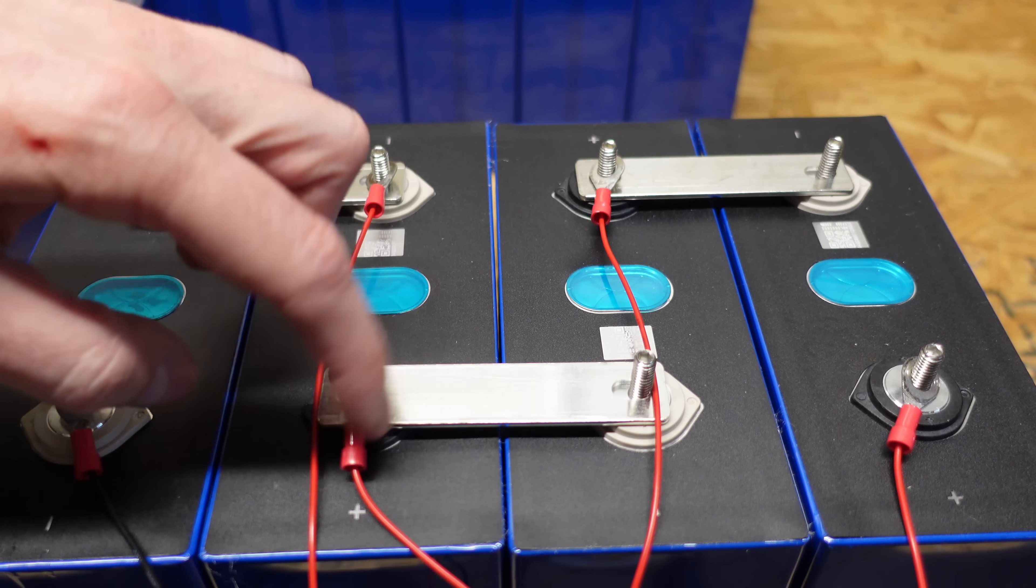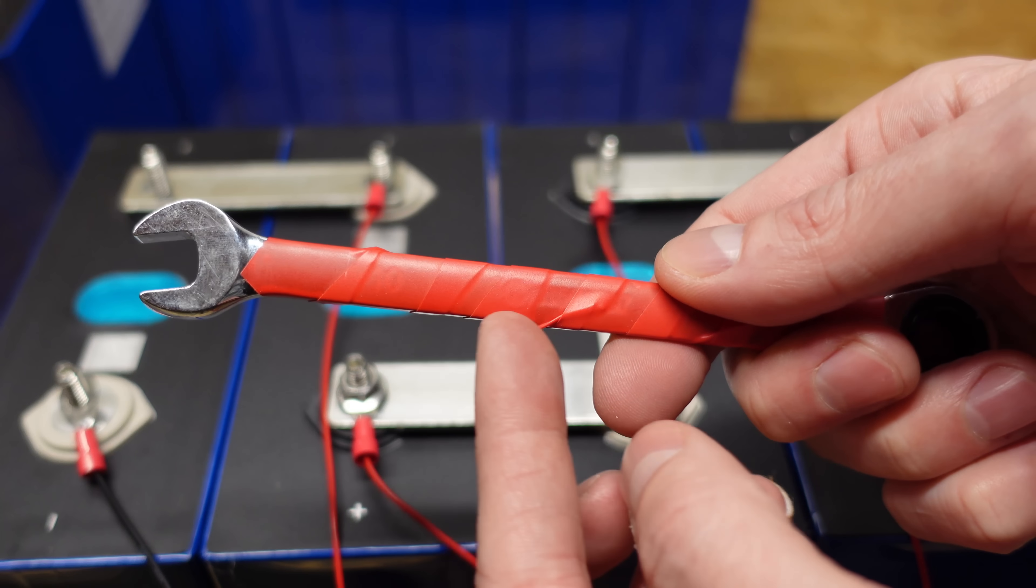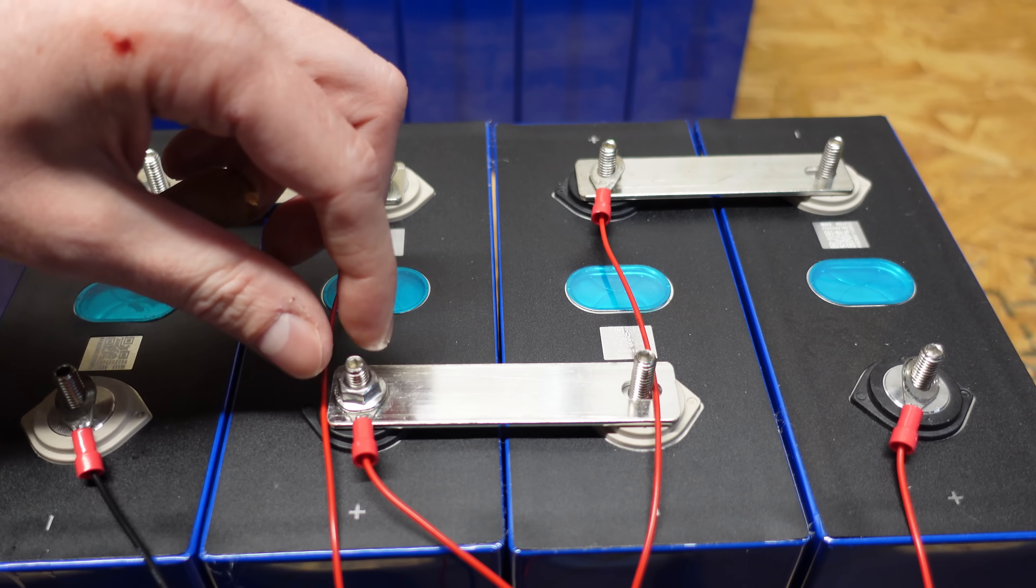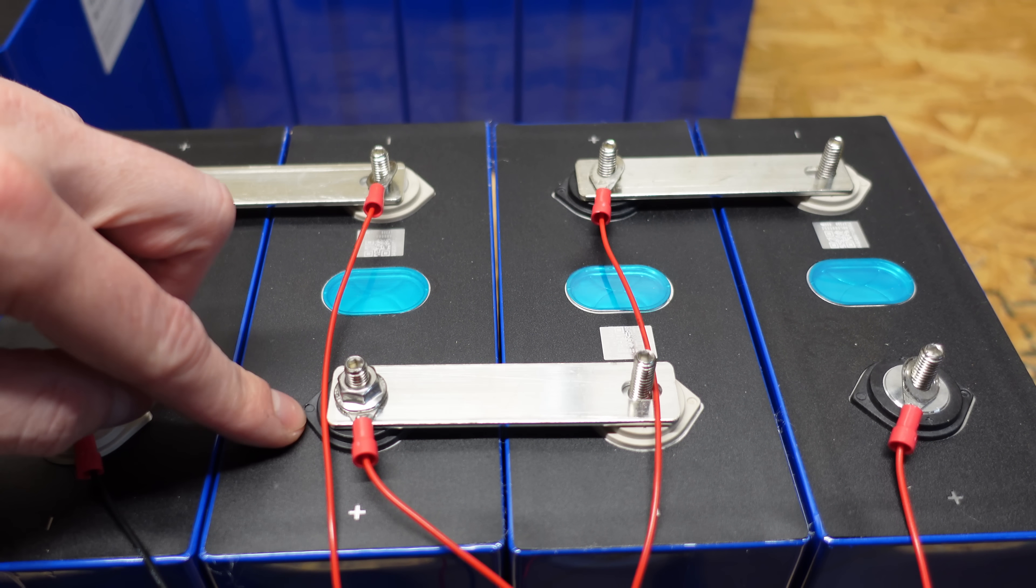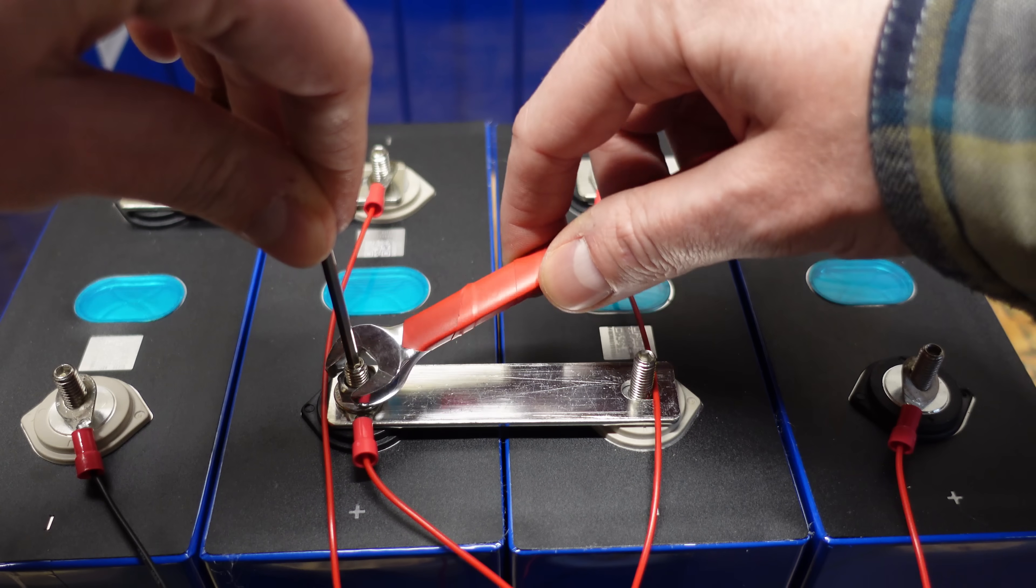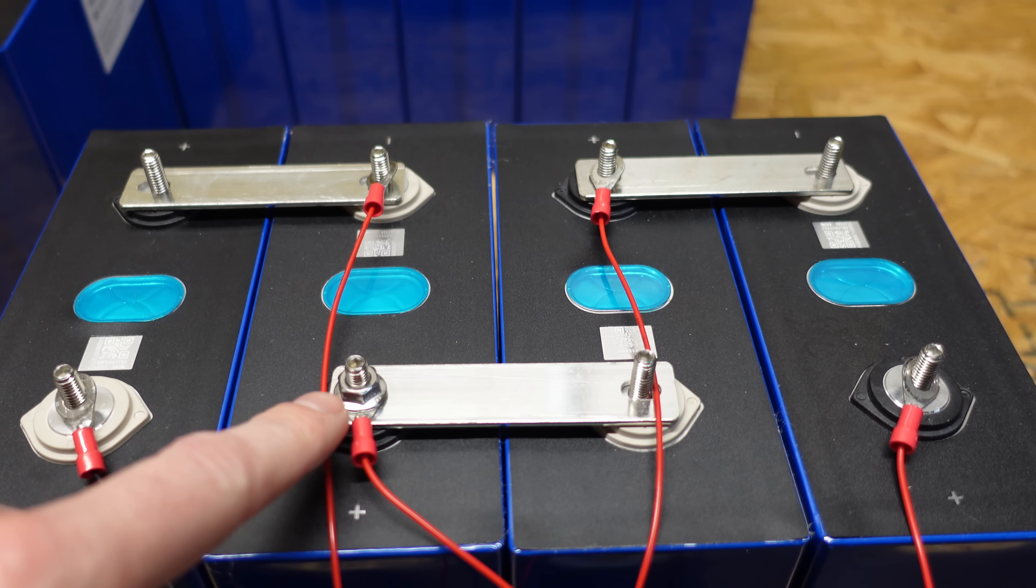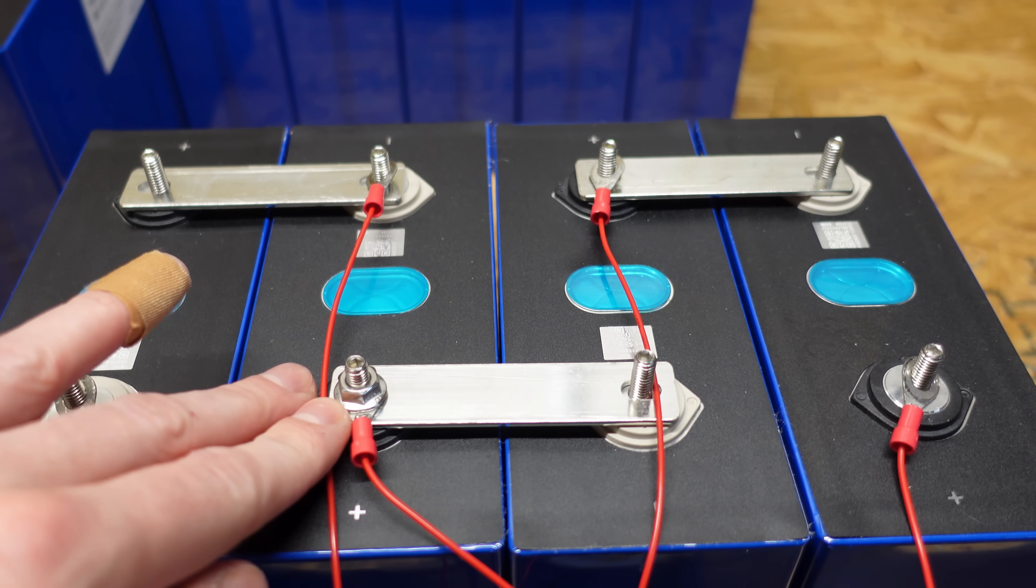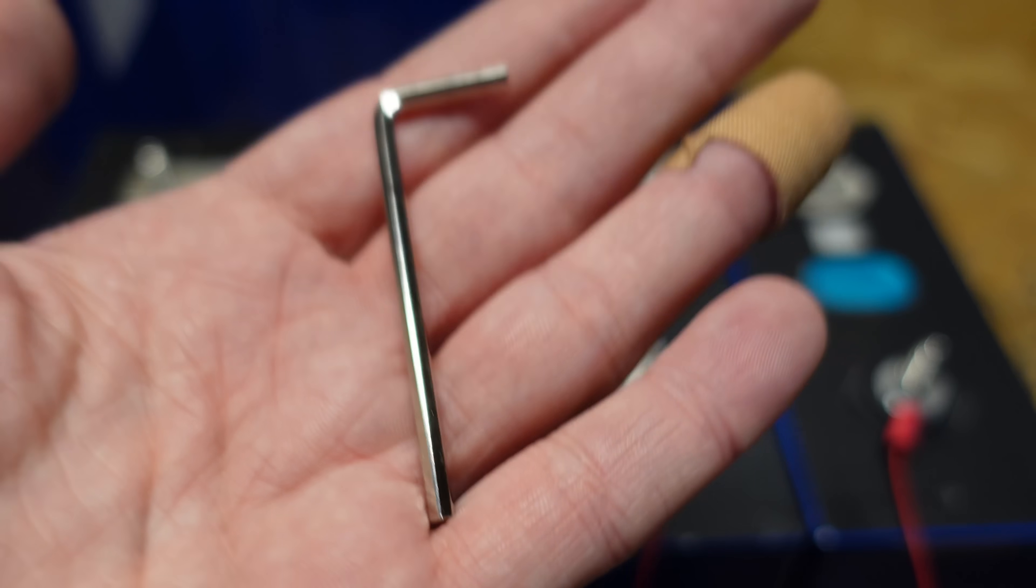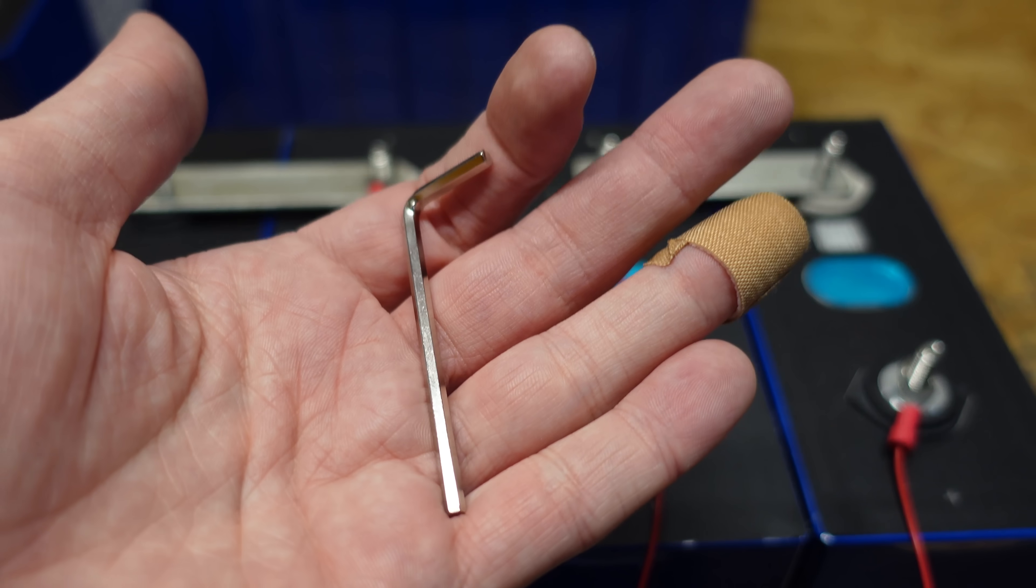Next, I'm putting on one of the flange nuts, hand-tightening it down. And then I have a 10-millimeter wrench that I insulated with some tape because you absolutely do not want to short out these batteries. And I also want to make sure as I'm tightening this down that I'm not threading this stud down into the battery and risk cracking the terminal of this battery. So I'm inserting the Allen head and just tightening it down by hand. Now, these are aluminum threads on here, so you do not want to over-tighten this. I don't know what the correct torque for these is. I believe it's either four or five foot-pounds. I'm not entirely sure. So I'm just hand-tightening them down for the purpose of this test. And this Allen wrench probably should be insulated as well.